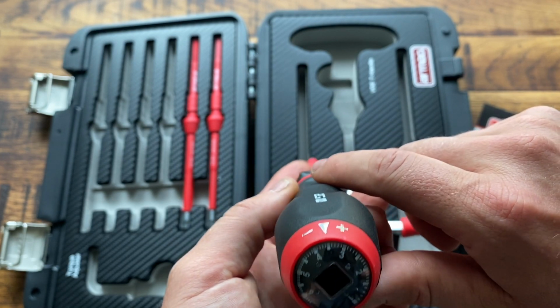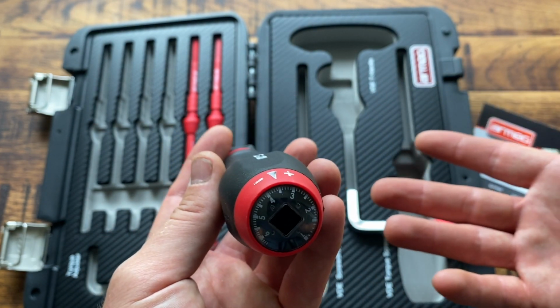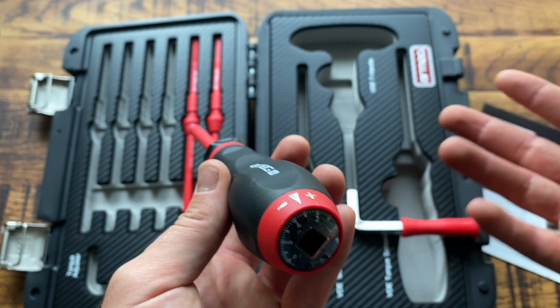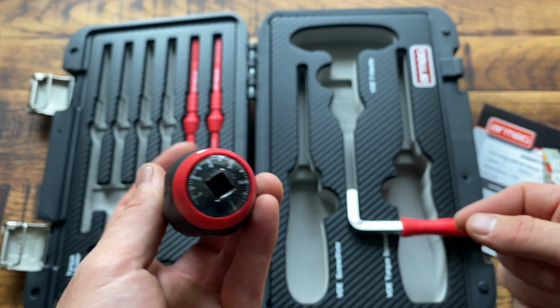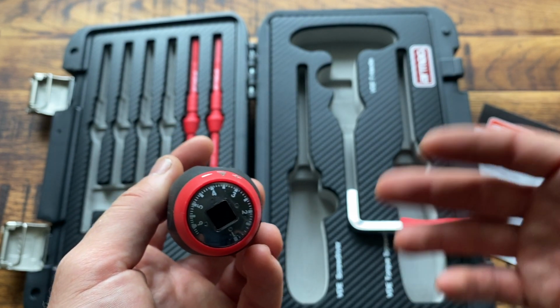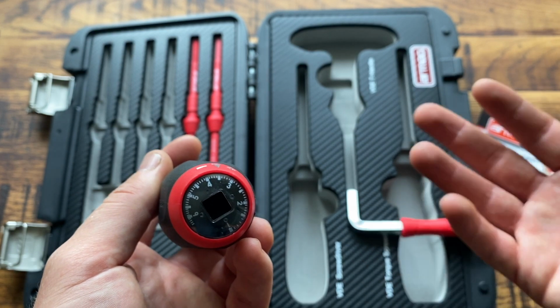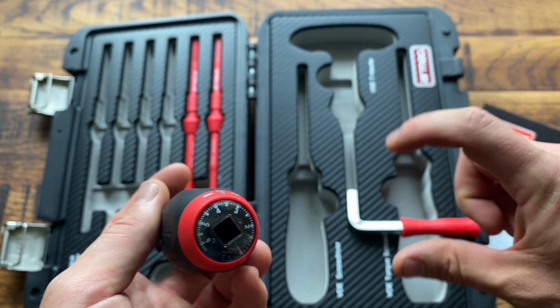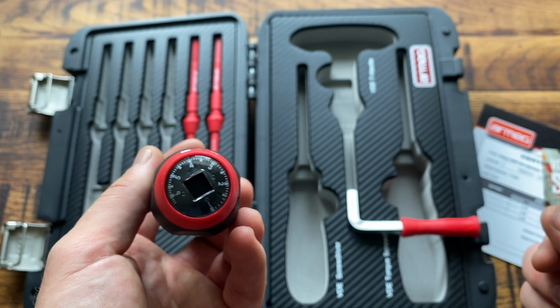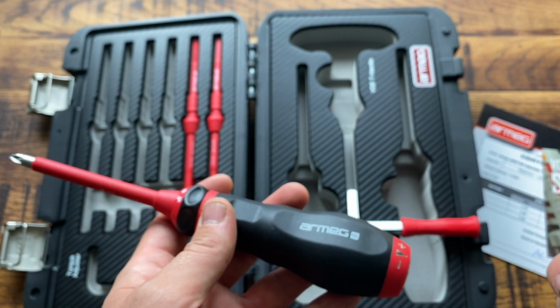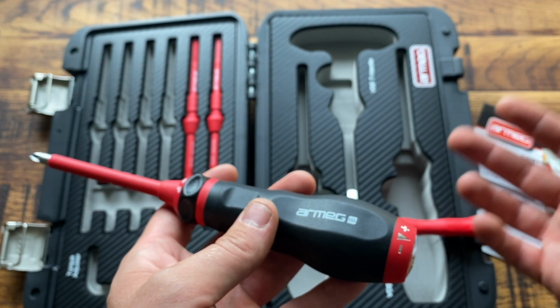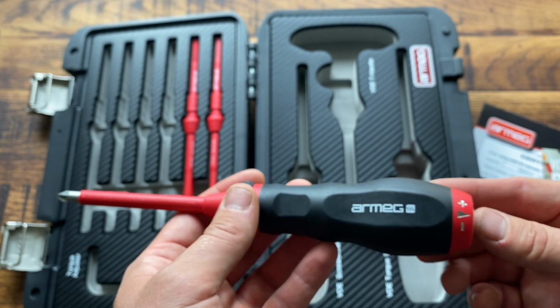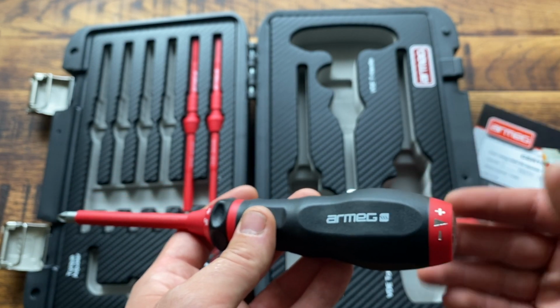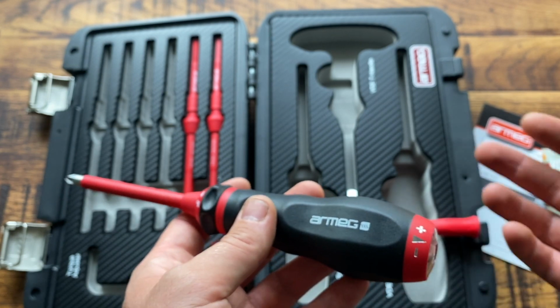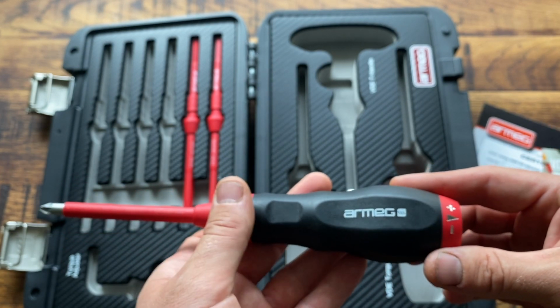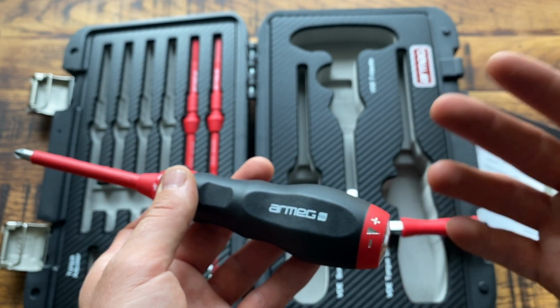With regards to torque settings themselves, how do you know what torque setting to use on what circuit breaker? Usually it's in the instruction manuals for the particular circuit breaker, consumer unit, or switch. For example, the Hager ones now have a little sticker on the front of the consumer unit which gives you all the torque settings for the various circuit breakers, main switch, neutral and CPC terminals - that's really handy. But if you can't find the details in the manufacturer's instructions, usually you can find it in a spec sheet online, which comes in handy when working on an existing consumer unit.